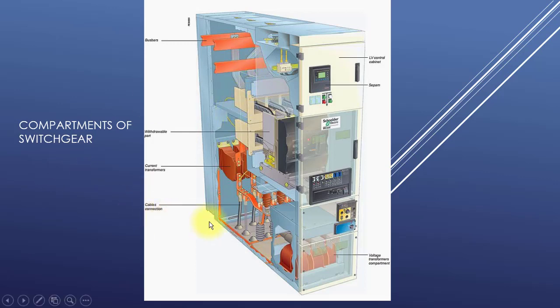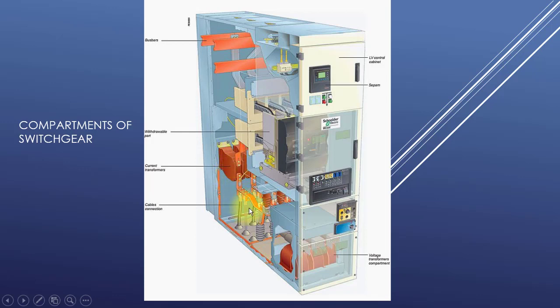The fourth compartment is here — you can see on the downside these are the cables coming in, so it must be a cable compartment. You can see the CT here, which has two connections — incoming and outgoing — so current is going through this device. Here you can also see insulators and VTs installed, confirming this is the cable compartment.